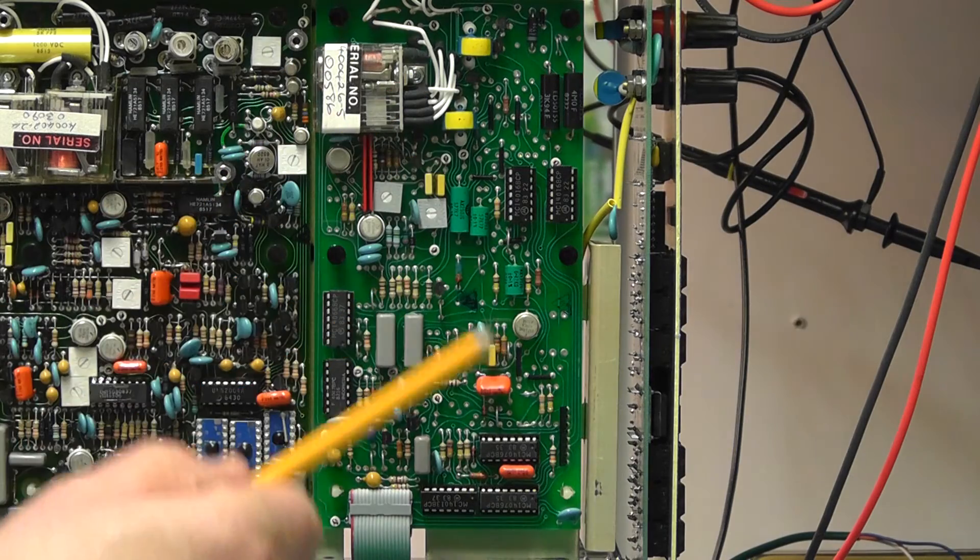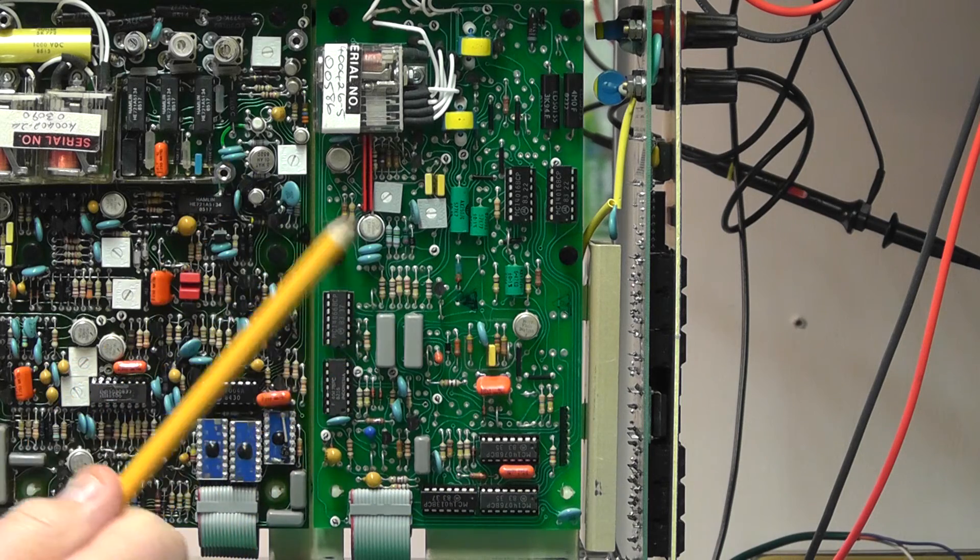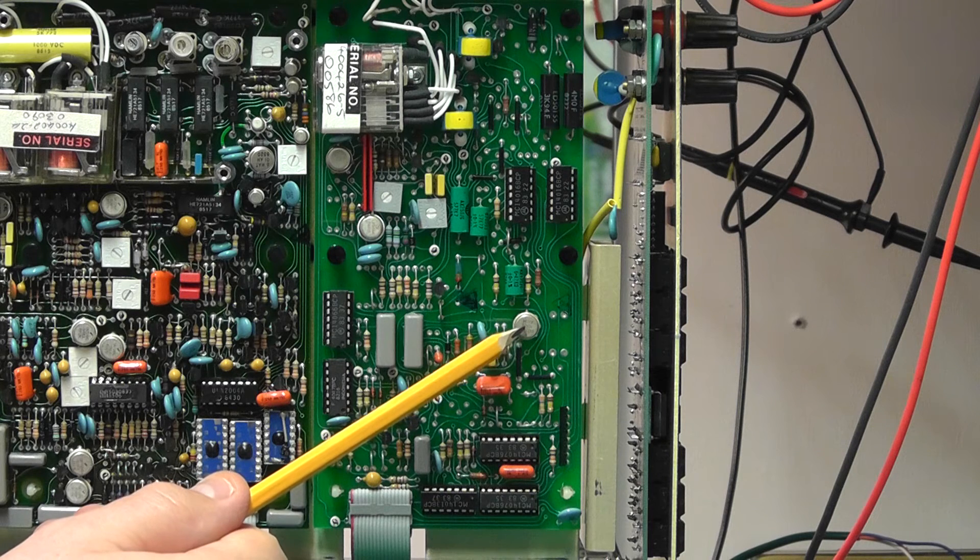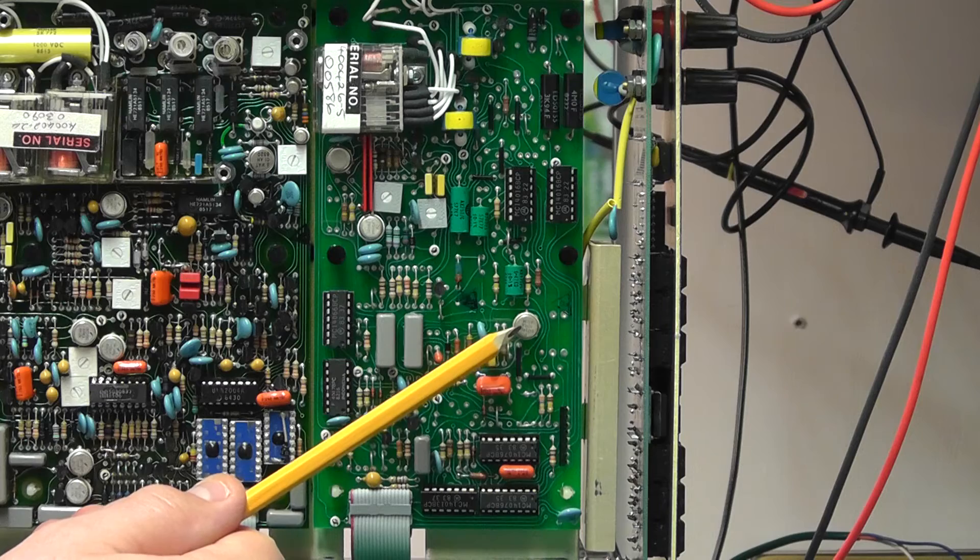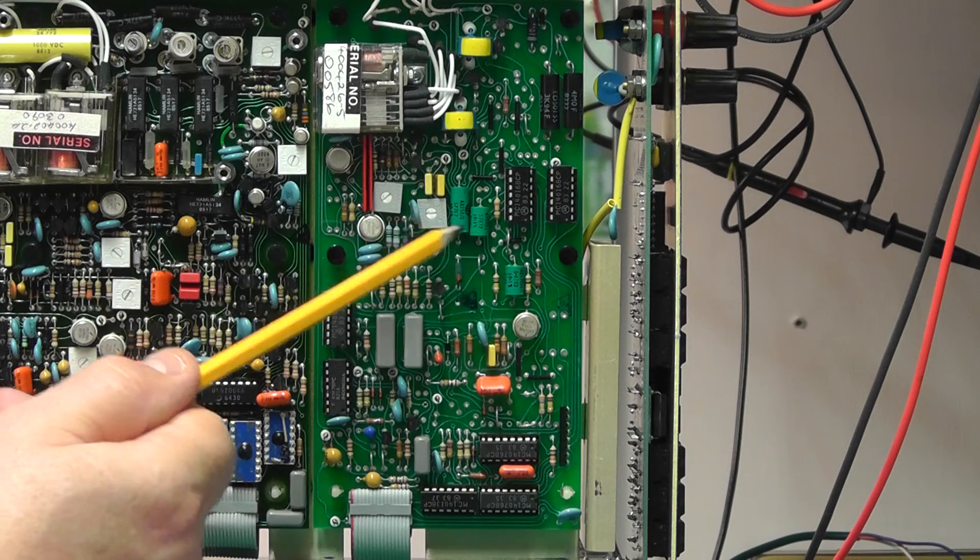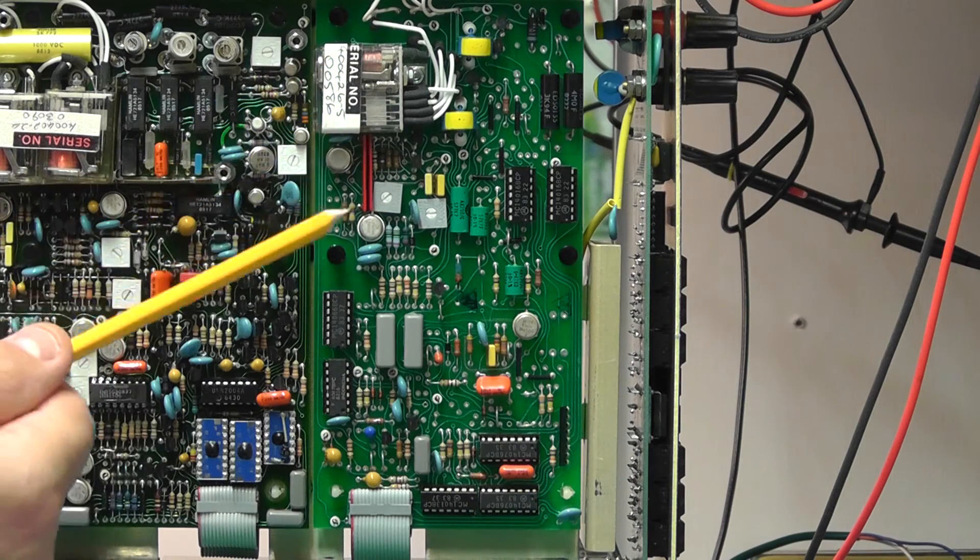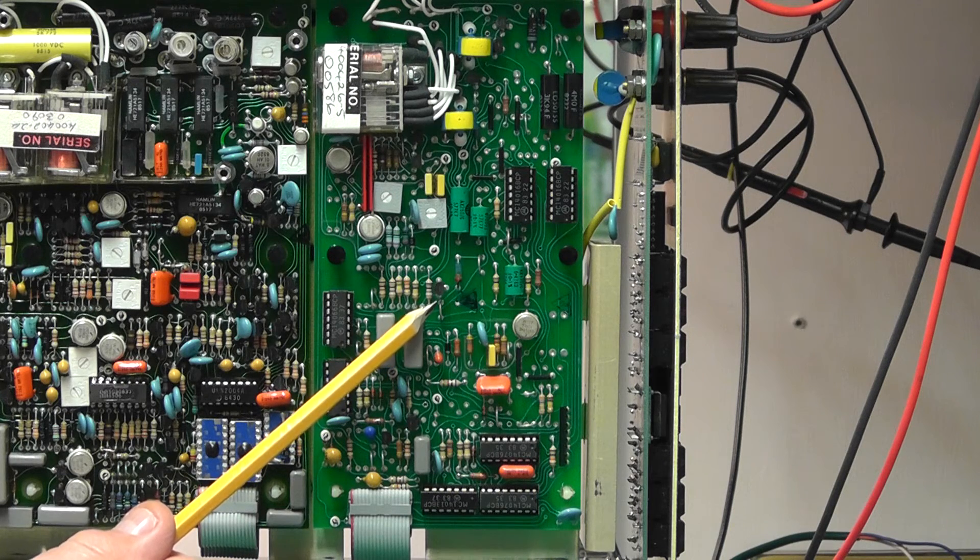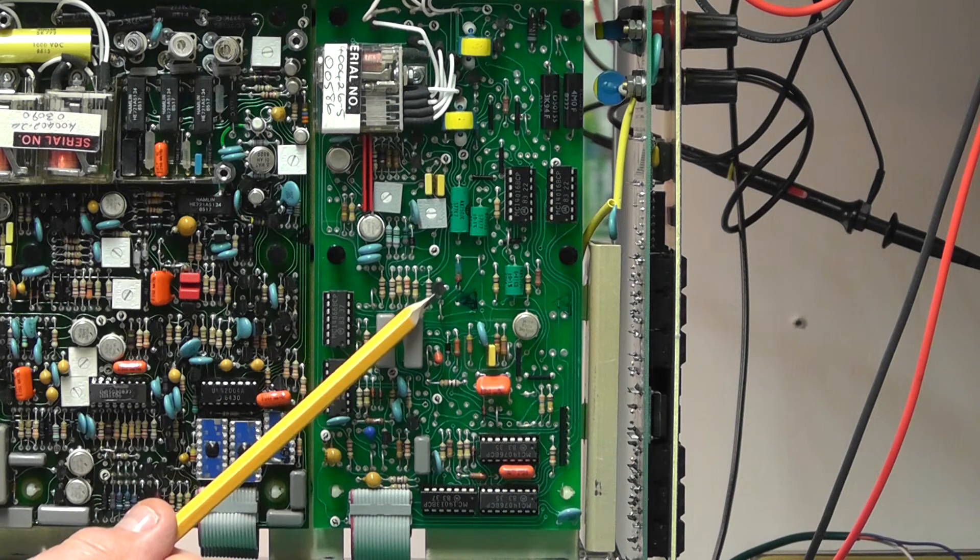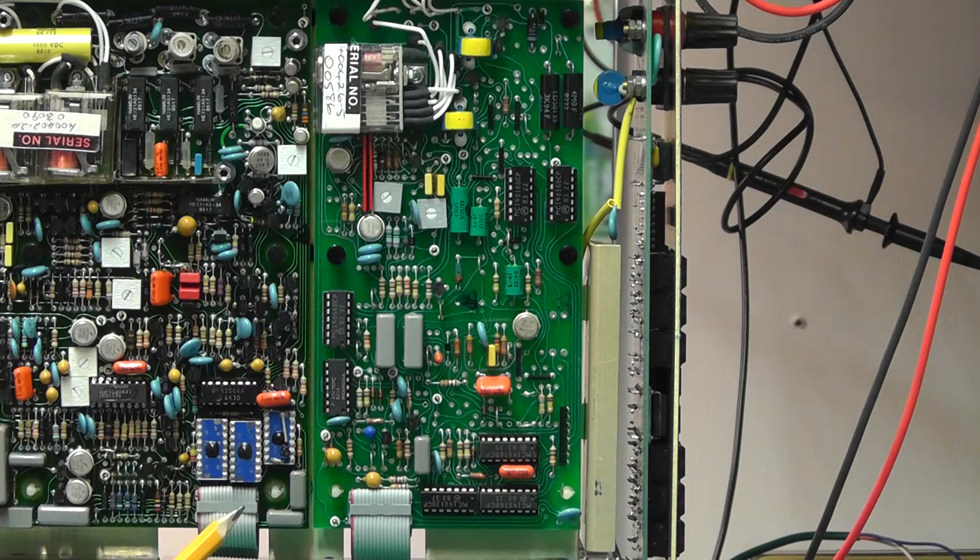Okay here's a closer look at the resistance module. The way this works is that they have an operational amplifier which is controlled to give a constant current, a very accurate constant current, by switching in some high tolerance resistors here. These green high tolerance resistors, there's some black ones up there. The relay is doing the switching and then basically what the unit does is it puts a known current through the unknown resistor that you're reading and measures the voltage and then supplies that voltage to the main microprocessor digital board and calculates the resistance of the unknown resistor.